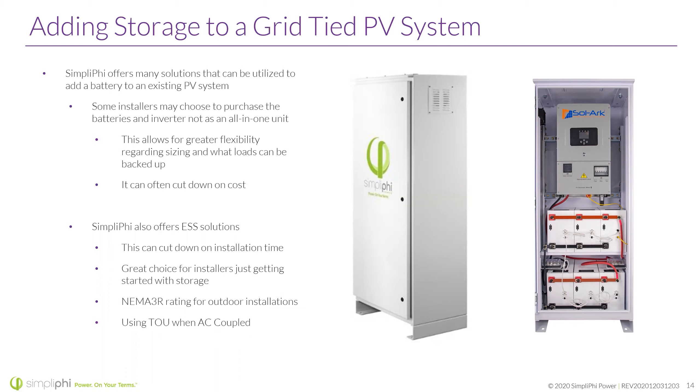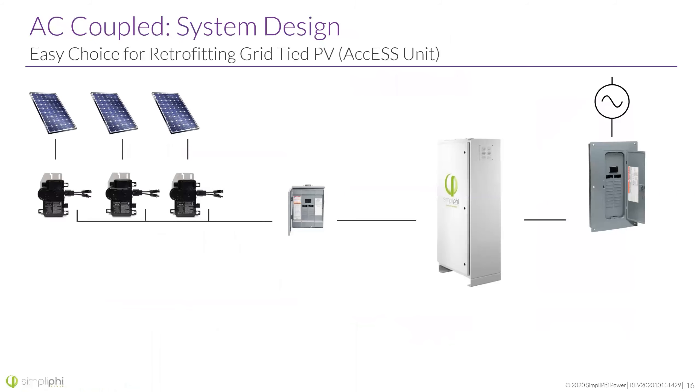These Access units are NEMA 3R rated, so they're for outdoor installation. For time of use and peak shaving, I really wouldn't recommend going AC coupled. SolArk is one of the inverters we use in our ESS, and while they do say you can use time of use when AC coupled, my general rule of thumb is: if you have the ability to go DC coupled, especially on a new system you're putting in, go DC coupled. You'll save yourself a lot of headache with time of use and peak shaving. If your customer doesn't care about that at all, don't worry about it.